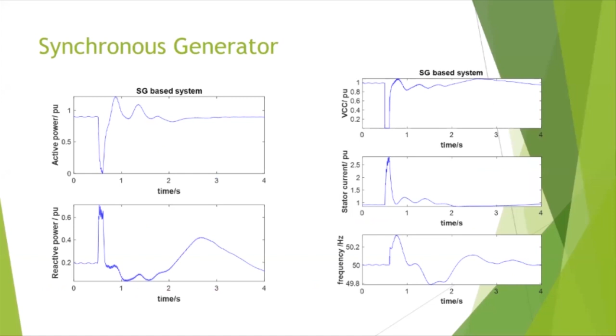What we are trying to do is get the submodule capacitors to store energy in the electric field, just like how a synchronous generator stores kinetic energy during the fault, and then releases it. So you can see the green curve doesn't store any kinetic energy, doesn't store any energy in the submodule capacitors, because we use the generic controls. The blue curve is a synchronous generator. So during the fault, it absorbs kinetic energy, increases speed, and then it releases after clearance of the fault. And the yellow curve, orange or whatever, is the converter with tuned controllers using the proposed technology.